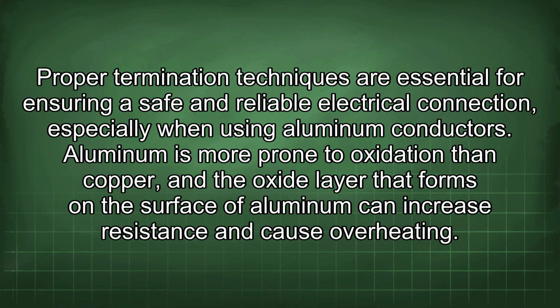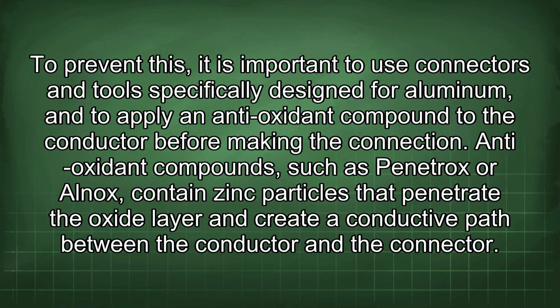voltage drop. Proper termination techniques are essential for ensuring a safe and reliable electrical connection, especially when using aluminum conductors. Aluminum is more prone to oxidation than copper, and the oxide layer that forms on the surface of aluminum can increase resistance and cause overheating. To prevent this, it is important to use connectors and tools specifically designed for aluminum, and to apply an antioxidant compound to the conductor before making the connection. Antioxidant compounds, such as Penetrox or Alnox, contain zinc particles that penetrate the oxide layer and create a conductive path between the conductor and the connector.